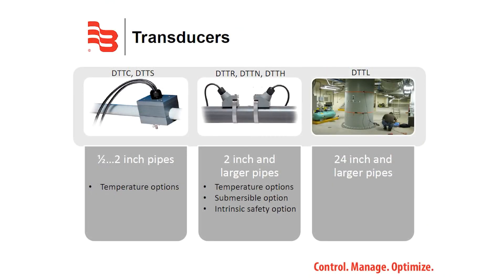The TFX line offers several transducer styles to fit your application requirements. The DTTC and DTTS transducers are designed for small pipe sizes from one-half inch to two inches and offer temperature measurement options. The DTTR, DTTN, and DTTH are designed for two-inch pipes and larger, offering temperature, submersibility, and intrinsic safety options. Finally, the DTTL transducer is reserved for pipe sizes 24 inches and larger. Transducers come in a wide variety of cable and conduit options.